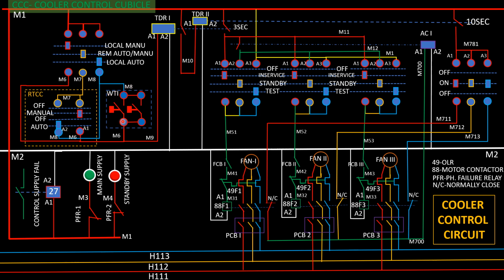Keep the switch at remote auto or local auto mode at the CCC, cooler control cubicle, and keep the switch at auto mode at the RTCC panel, remote tap changer and cooler control panel. Keep the switches here at in-service mode. Keep this rotary switch at on mode to give power to the AC1 contactor for powering the standby fan.